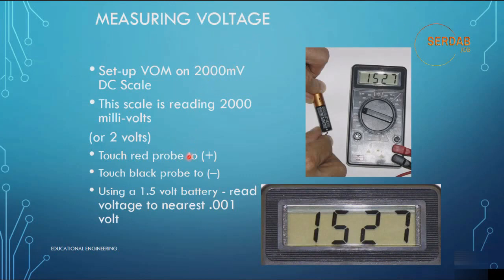So as you can see here, we are using the millivolt range, and we are setting it here on the volt ohm meter. As you can see now, in this 1.5 volt battery, we can read the voltage to the nearest 0.001 volt, and the reading is given as 1527 millivolts. It's equal to 1.527 volts. So it's the same, but you just make the resolution much higher.